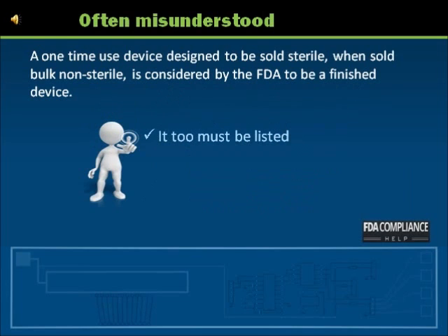Another often misunderstood item is the one-time use device sold bulk, non-sterile, to companies that package, sterilize and distribute. These non-sterile devices are considered a complete device by the FDA and must be listed.